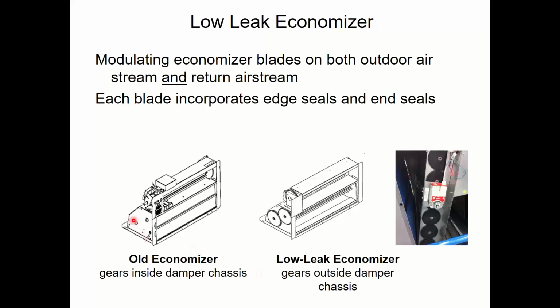If you have a regular damper, the gears, these little gears with the little teeth on them, right? The gears will be on the inside over here in the airstream. If I have a low leak one, the gears move from the inside of the airstream to the outside of the airstream. The reason being, when they're on the inside of the airstream, gears obviously have to be able to move. If they have to be able to move, it's difficult for them to be perfectly tight. And if they're not perfectly tight, it's really hard to get to the low leakage.